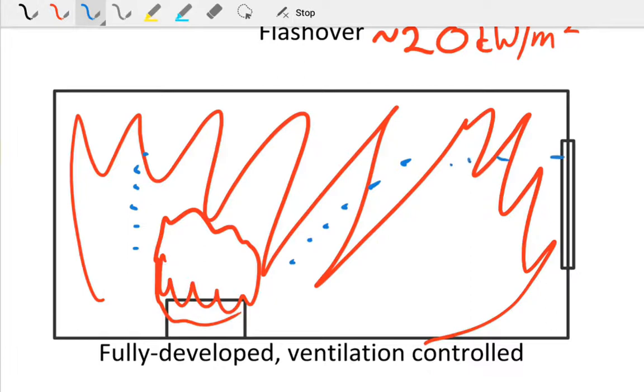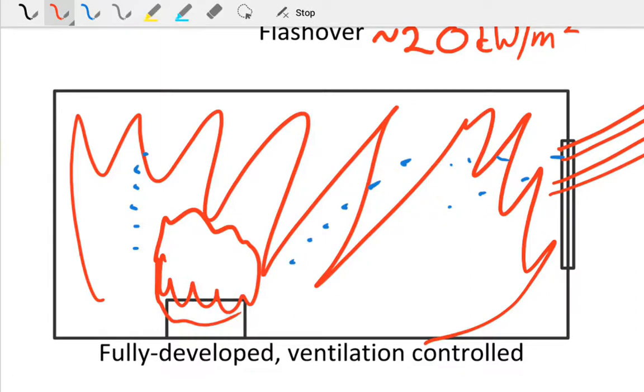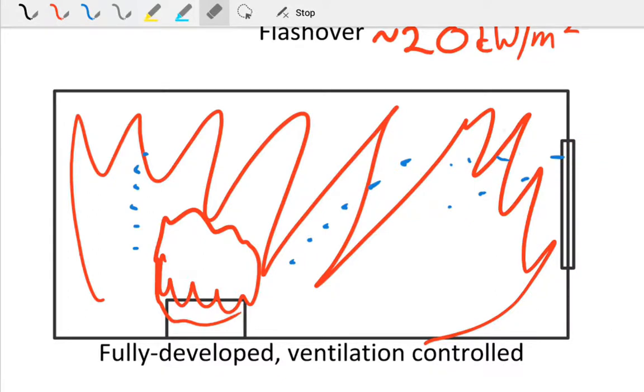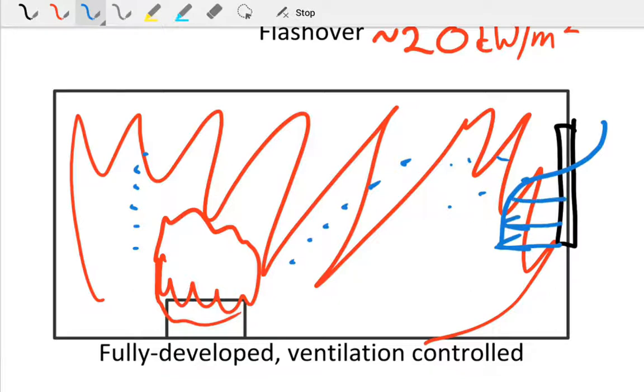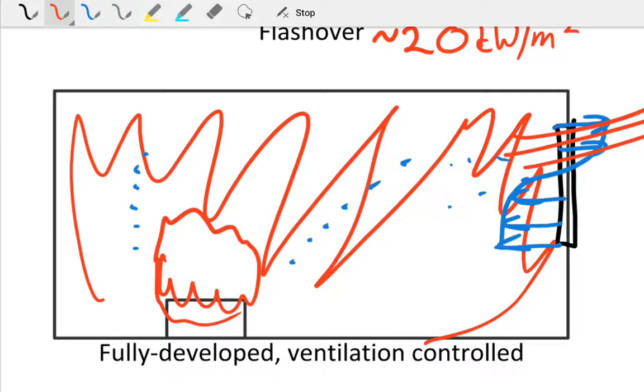They actually go looking for air, and then what you can have is the combustion actually occurring outside the window. You'll have flames emerging from the windows. Depending on how many windows there are and their shapes and size and where they are, the profile of air coming in and out of the room will change. Let's say we've just got a window here—there's our window. We could have a profile that looks something like that with air coming in the bottom and then emerging out the top as flames are pushed out. If there are multiple openings, you may see that it could just be a pure flame plume coming out the door.